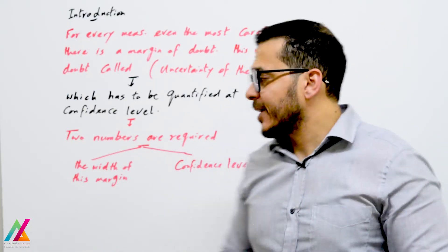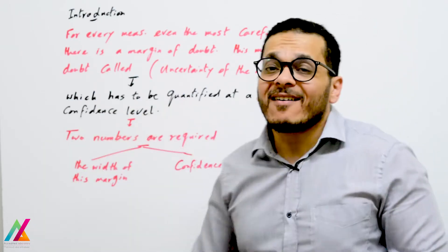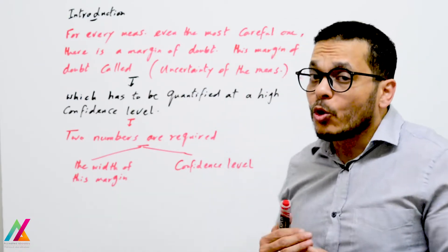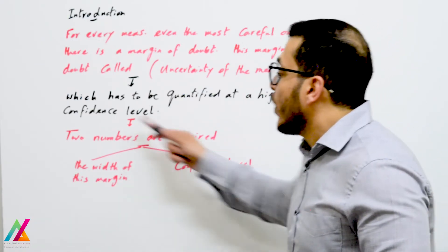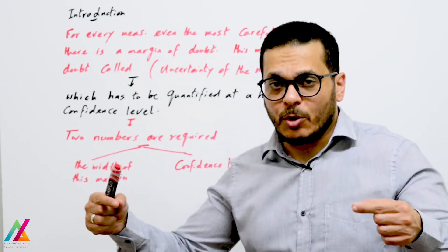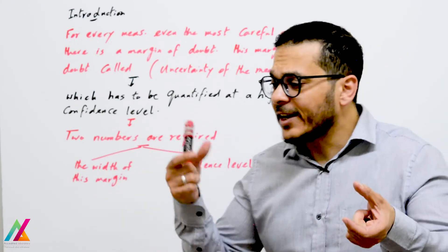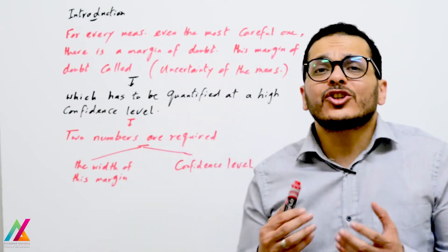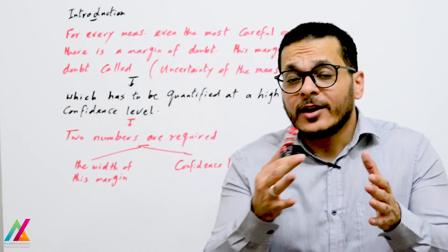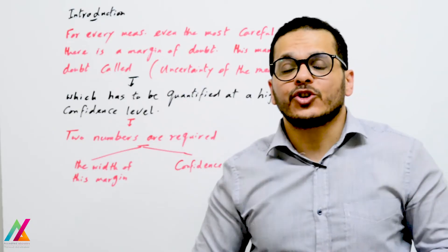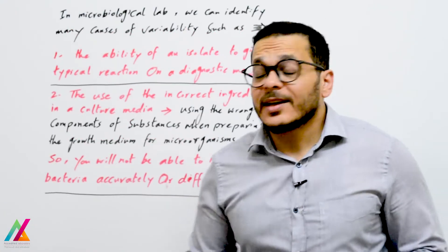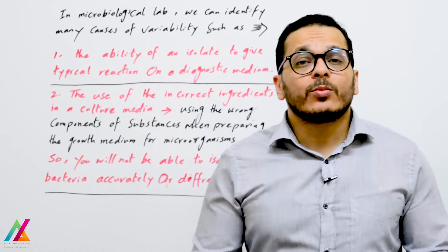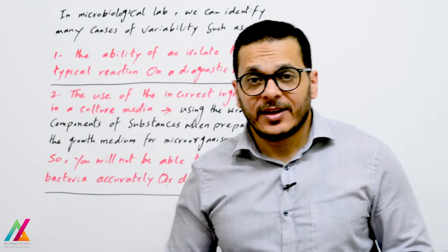This margin of doubt shall be quantified at a high confidence level to give a reliable result. Two numbers are required to quantify this margin of doubt: the width of the margin — how wide the range is — and the confidence level — how confident you are that the true value lies within that range after addition of the measurement uncertainty.